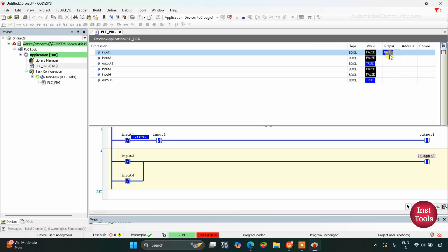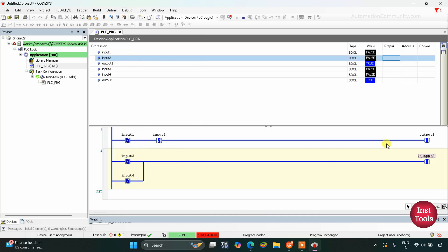For Output 1 to be true, both inputs should be false. If I turn Input 1 on and go to Debug and Write Values, you can see Input 1 is true and it will not allow signal to pass, so Output 1 becomes false. Similarly if we turn on Input 2, as a normally closed contact it will not allow signal to pass, and Output 1 gets off. If both inputs are on, Output 1 remains off. When both inputs are turned off, Output 1 becomes true again.